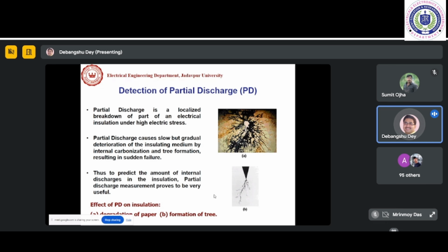But in that void, local discharge will occur, meaning some local ion discharge will occur. If we allow that discharge to persist, these images will show you what happens: from that particular void, gradually that insulation will degrade, becoming very poor and weak, and eventually a dead short circuit or fault may occur.